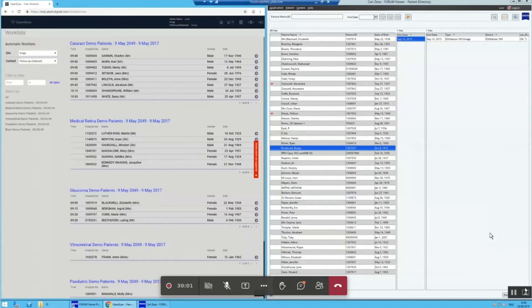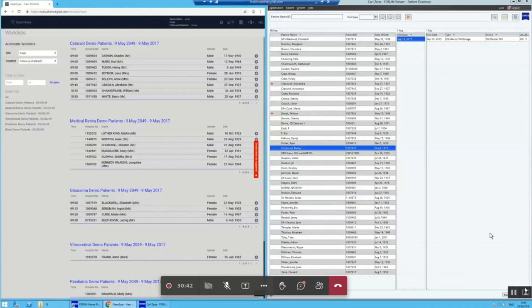We have our imaging on Zeiss Forum, which integrates very well with OpenEyes and the hospital system. Our clinic lists are pushed from the hospital system into both OpenEyes and Zeiss Forum, and from there into the devices. So when a patient arrives at a cataract clinic and goes for biometry, the device already has all their demographics and details — the technician just selects the correct patient rather than typing on a small keyboard. Once biometry is done it's pushed into the correct record in OpenEyes, eliminating another potential risk around wrong patient data.